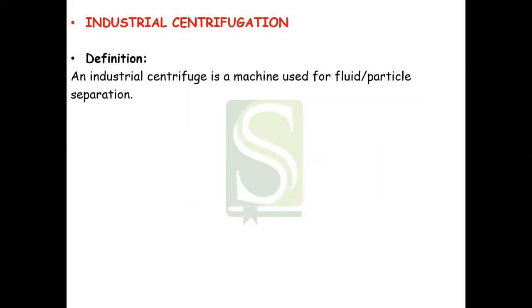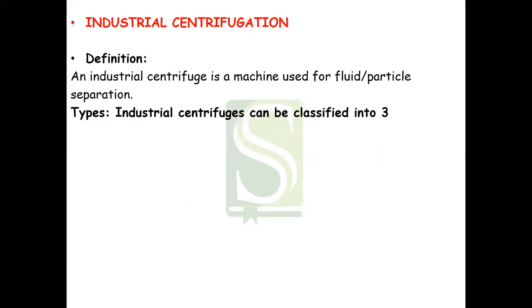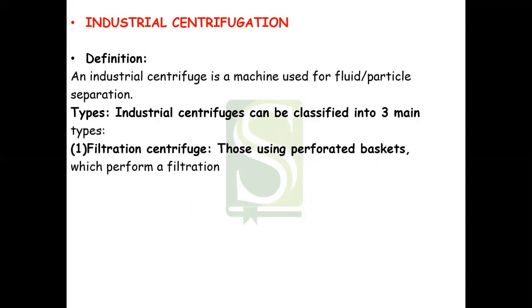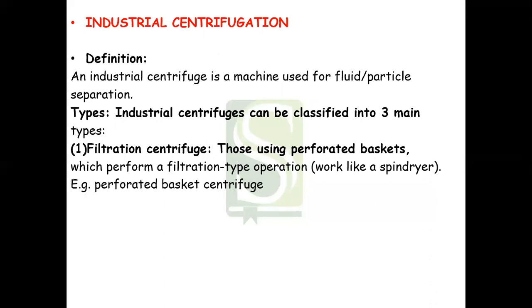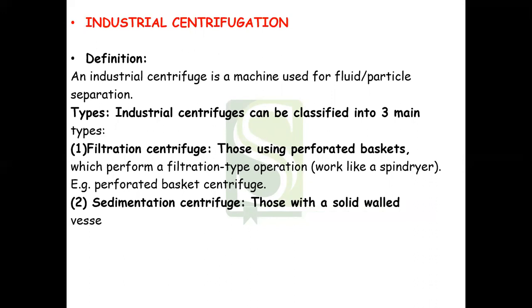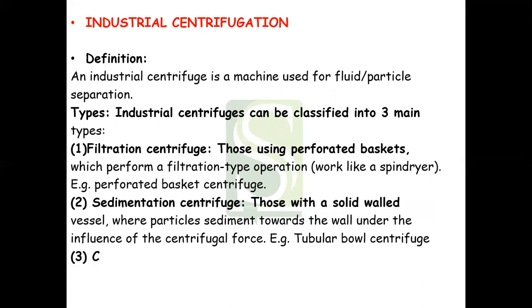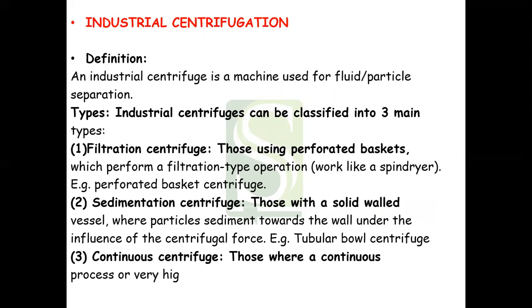An industrial centrifuge is a machine used for fluid-particle separation. It is of three basic types. The first is the filtration centrifuge, which uses perforated baskets to perform a filtration-type operation — they work like spin dryers. Example: perforated basket centrifuge. The second is the sedimentation centrifuge, with solid-wall vessels where particles sediment toward the wall under centrifugal force; example: tubular bowl centrifuge. The third is the continuous centrifuge, used where continuous operation or very high capacity is required.